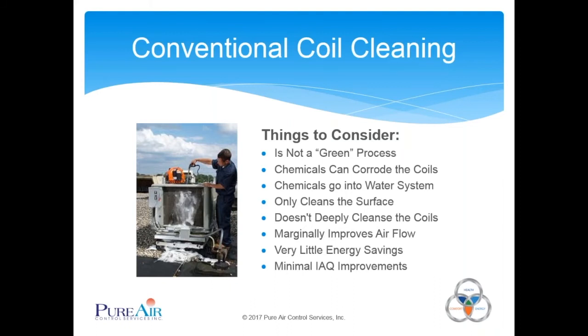Here are some things to consider about conventional coil cleaning, which you may already be using. Traditionally, this method involves a chemical foaming agent or detergent to foam up the coils, then using a garden hose or pump sprayer once it's worked on the coils to hose it out. Typically this hasn't been a green process.